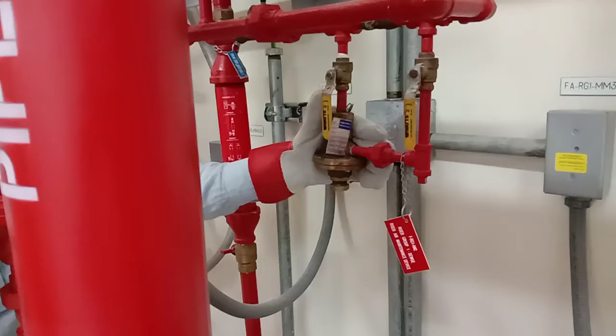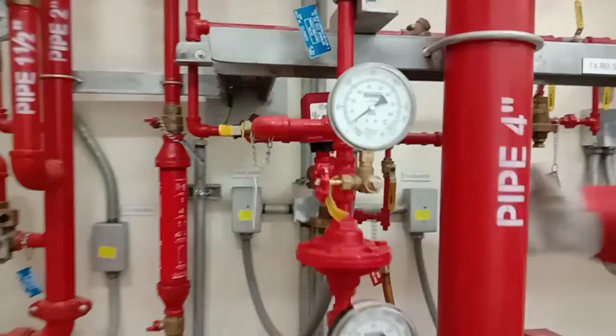Now we have a PS40 supervisory switch, right? This supervisory switch will give us the high pressure indication and low pressure indication to the panel. If the pressure is low, it might be activated without fire, so we have to be careful regarding those. So we have to get some signal to our panel. At the back of the switch, we have a PRV. If you can show that one, we have a PRV with the marking and all. Here we have a PRV, right? These are factory set to something like 20 psi or 30 psi based on the requirement of the data sheets. If the pressure is high, it will open and discharge the water to the discharge area to relieve the pressure.